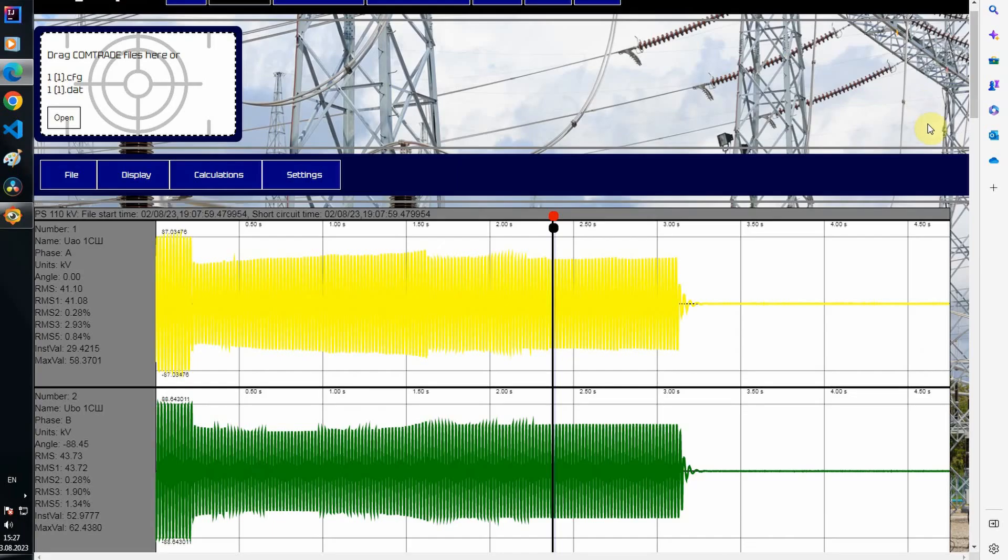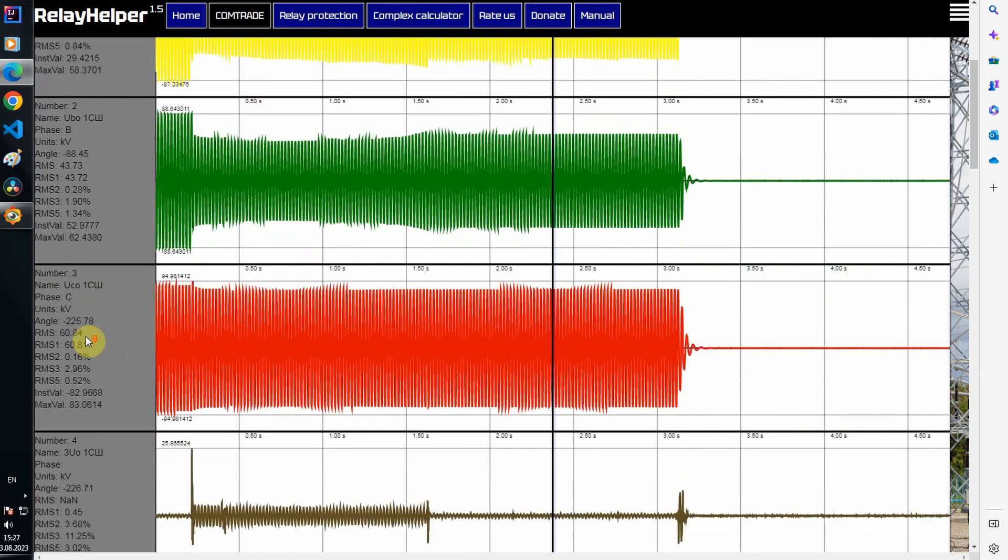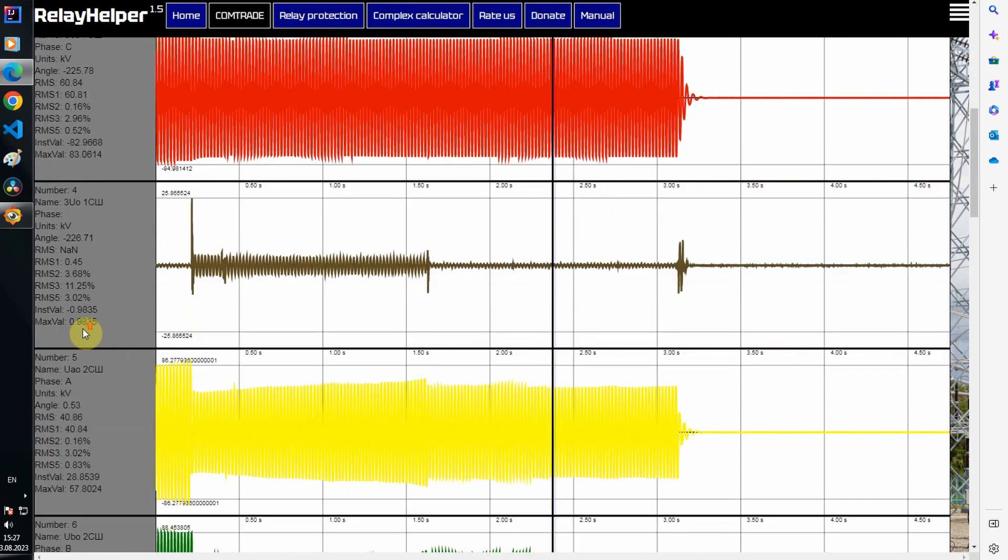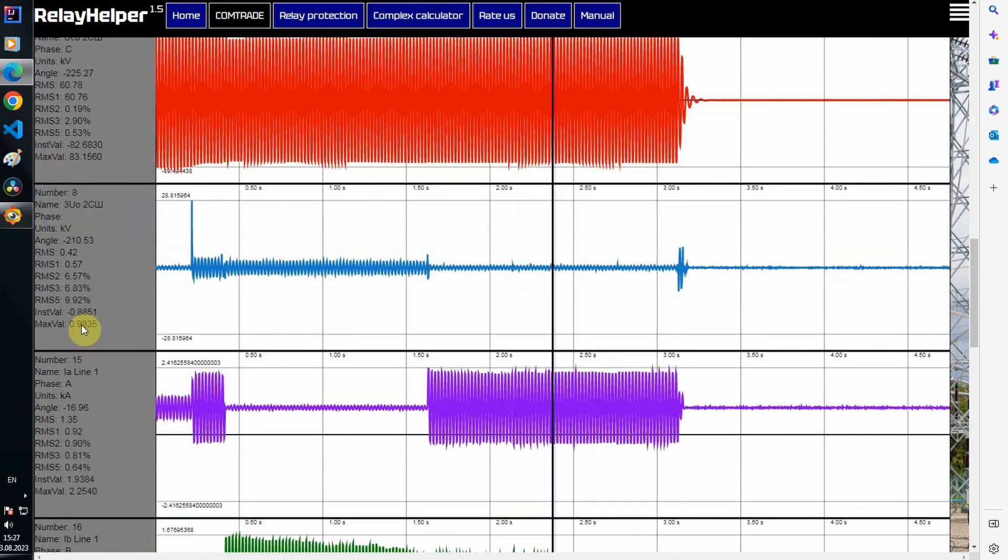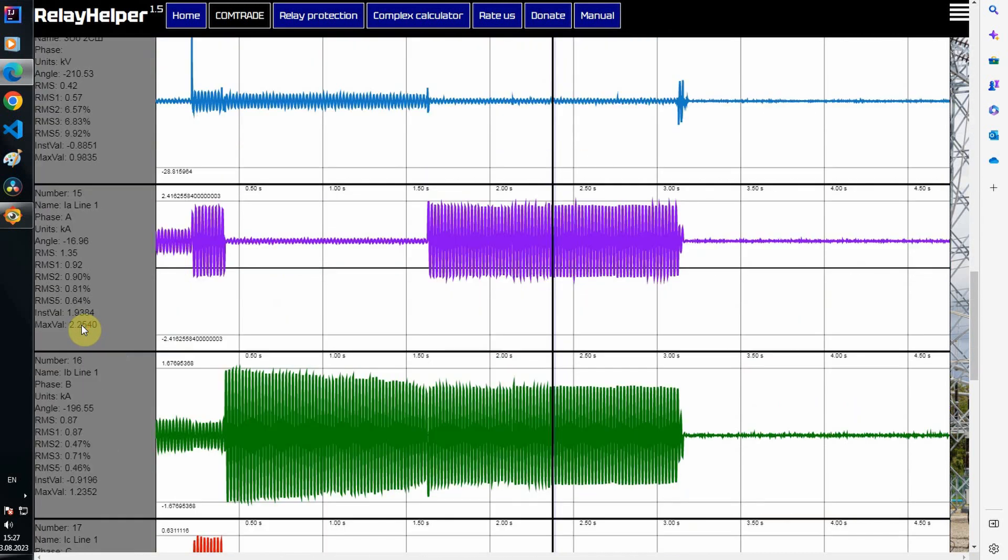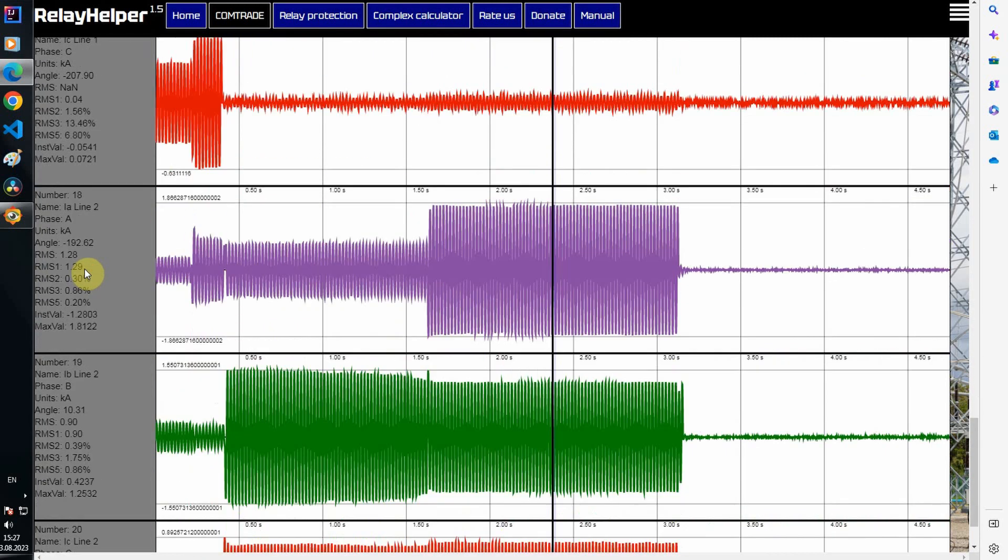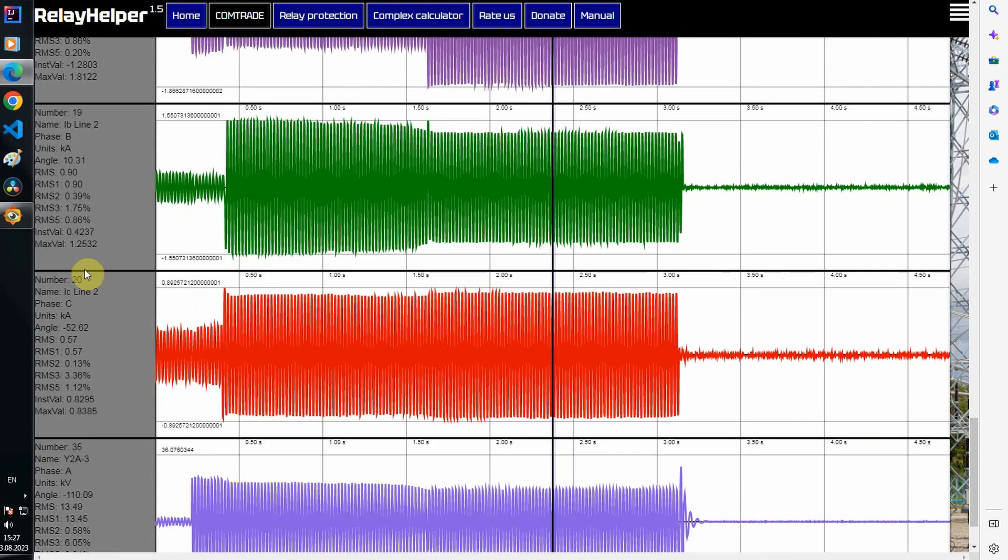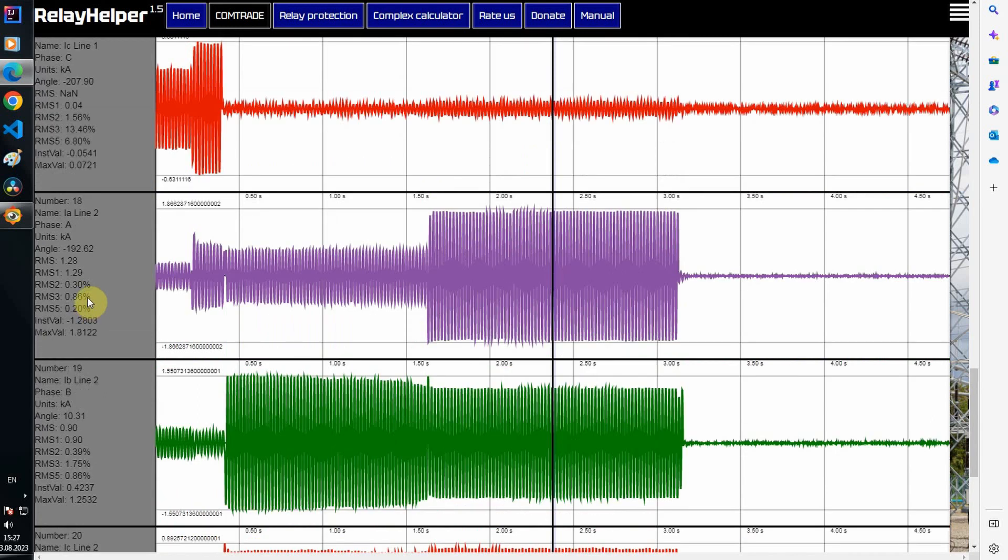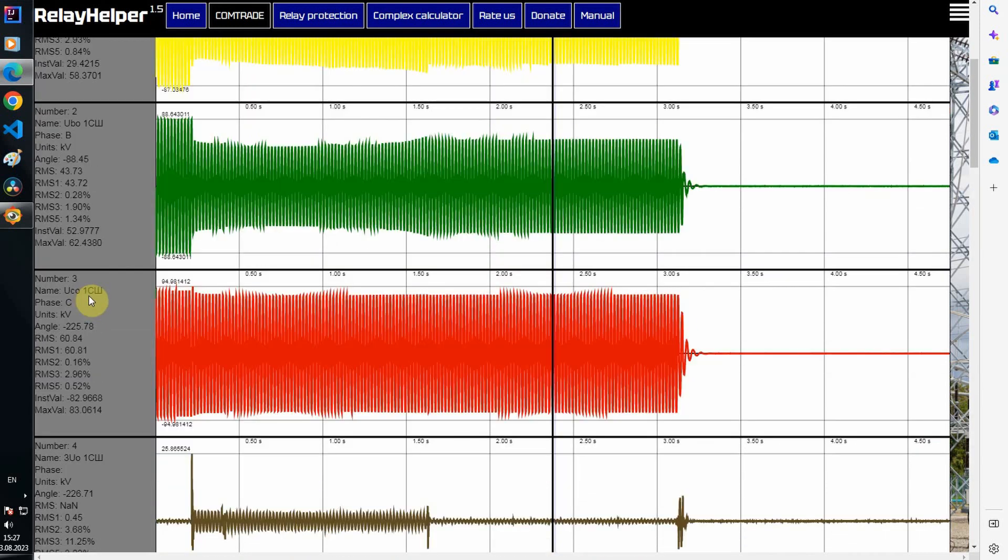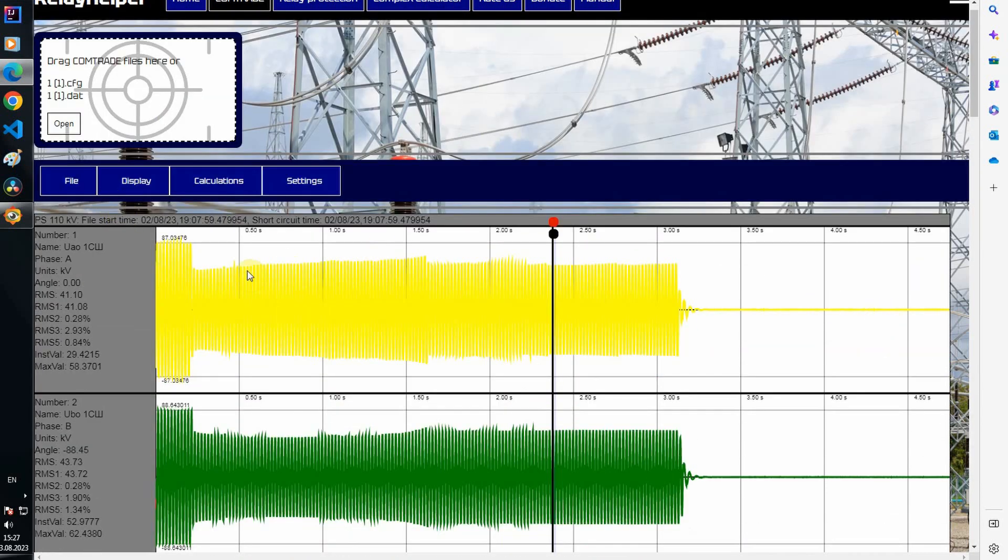First line voltage, second, currents of the first line, second. I've hid all channels from other feeders so they don't get in the way. As you can see, there was a complete shutdown of the substation.